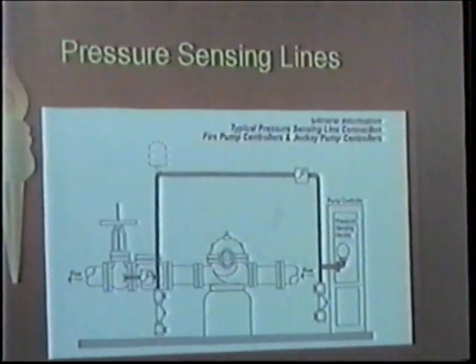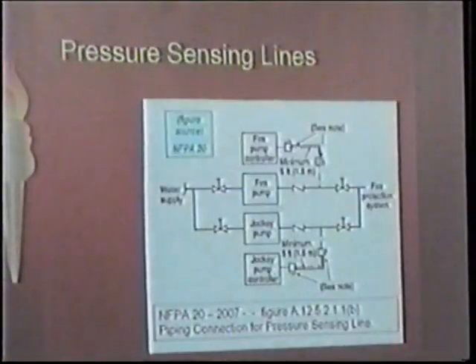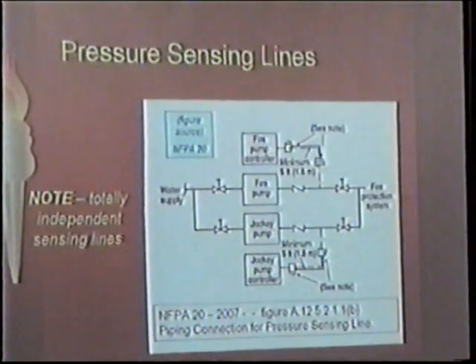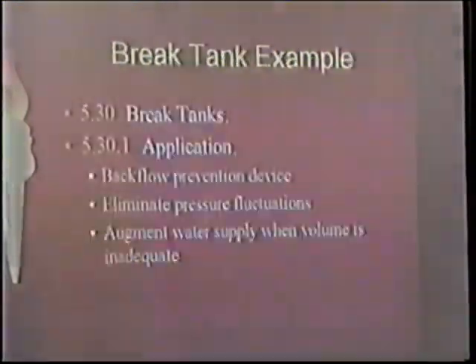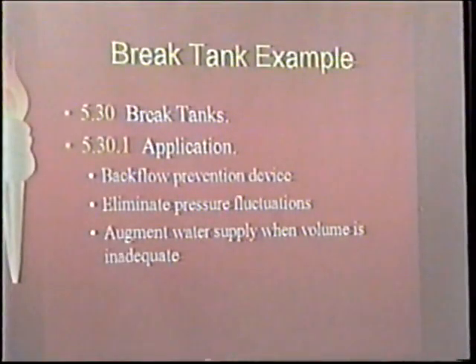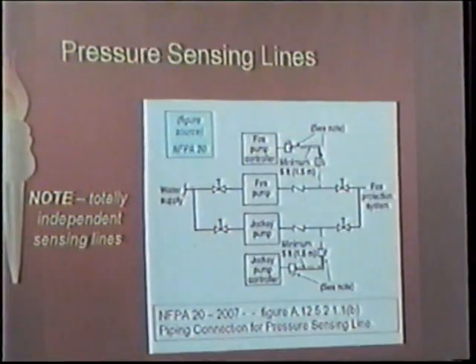There's a typical diagram that comes with every fire pump controller. It shows the proper placement of that. And here's the one that's actually in NFPA. If I have an issue with anything here, it's this connection point on the sensing line back to the pipe. I find a lot of places where some of the contractors are still wanting to put that out here on the system.